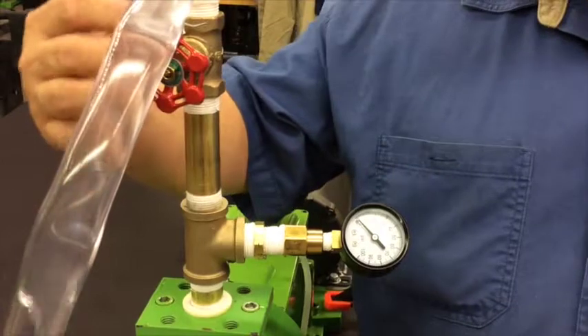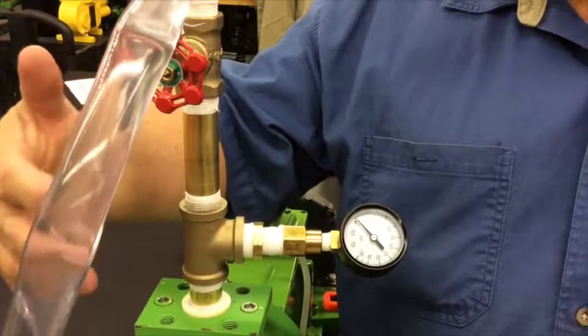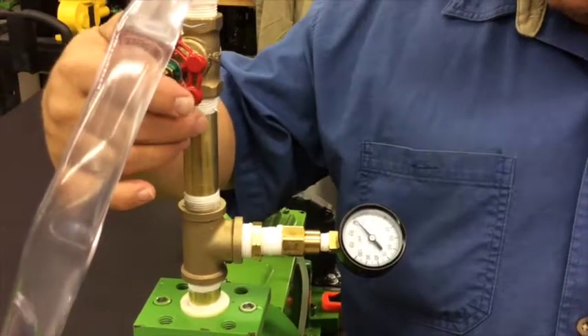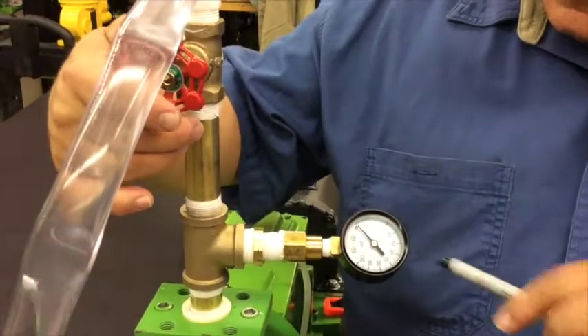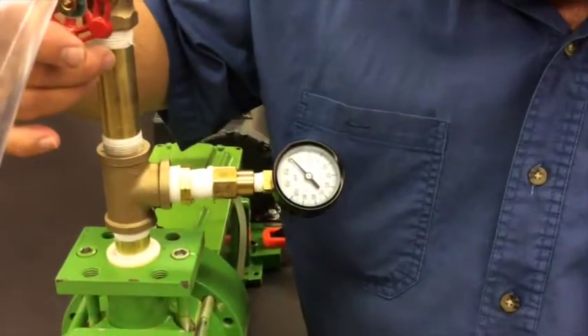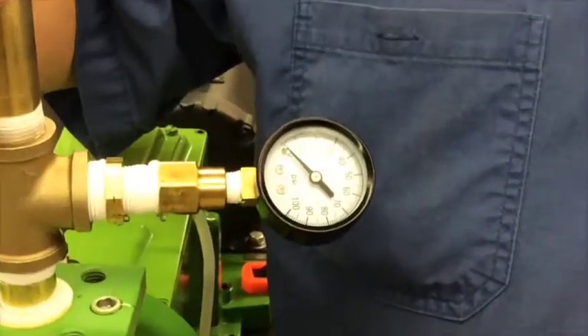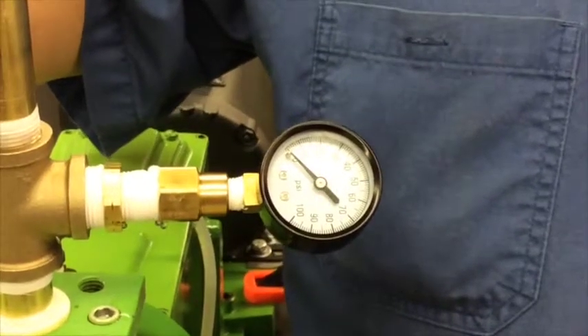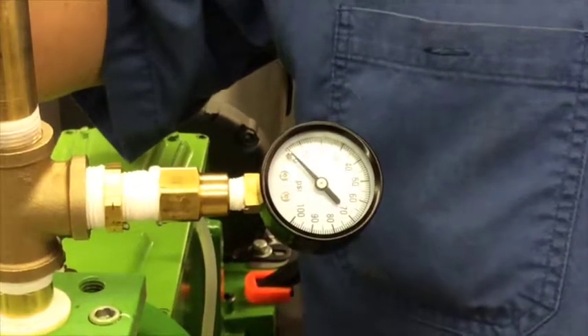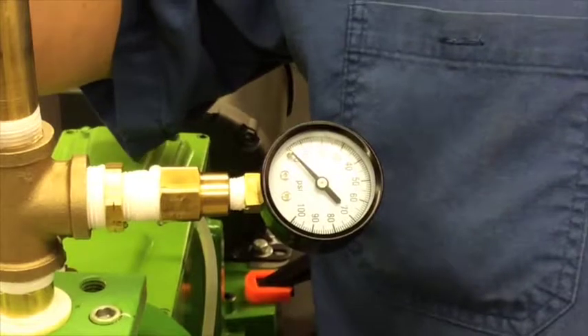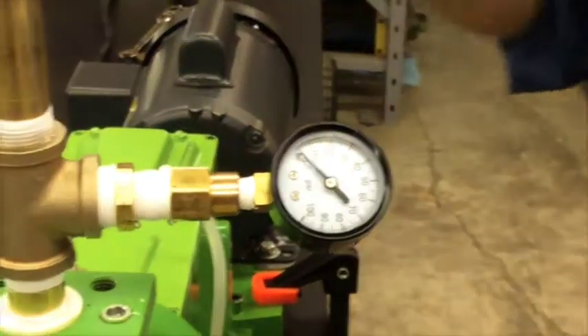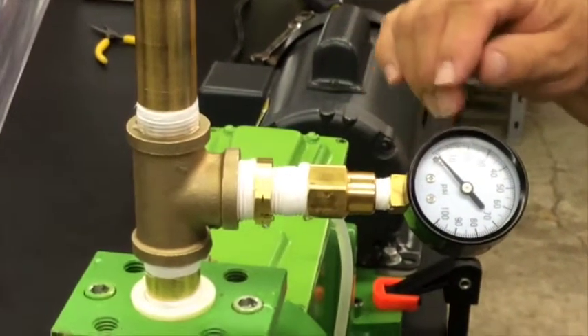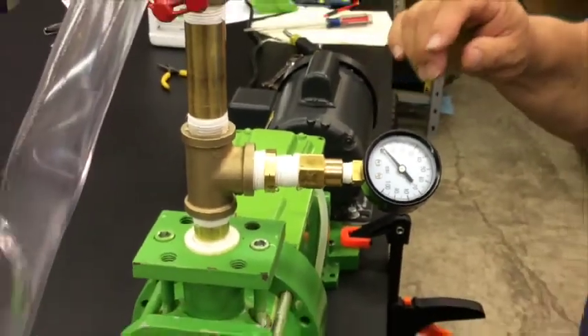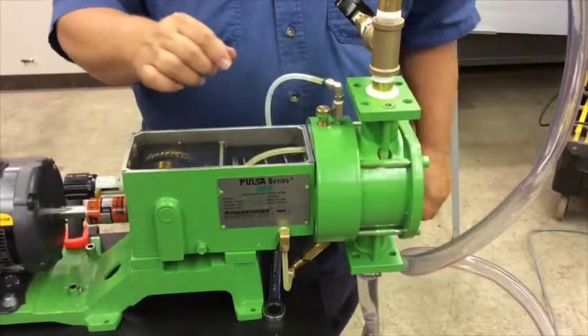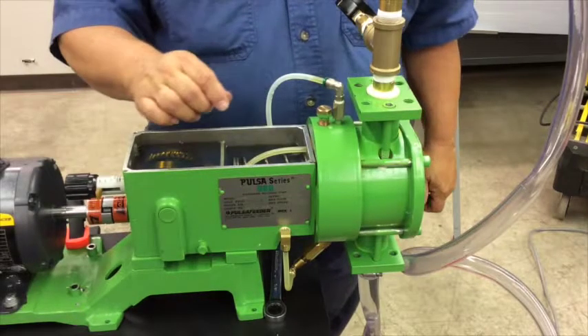So as you can see, I'm getting flow out of the discharge side of the pump. And what I've done is I've closed down this valve. So now on every stroke, I'm getting approximately 20 PSI back pressure on the system. Pump looks like it's pumping really well right now. So the next step that we're going to do is finally adjust the hydraulic bypass.